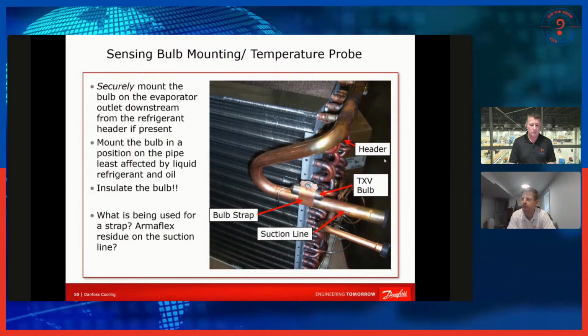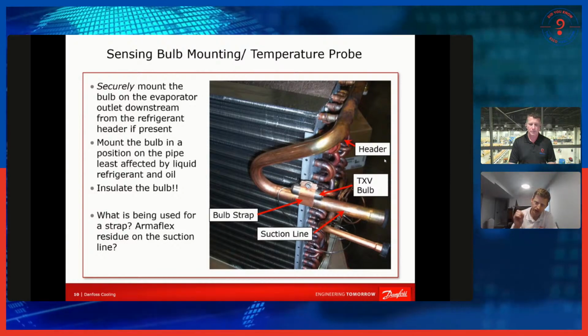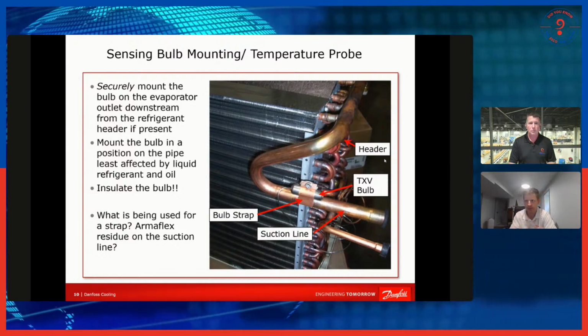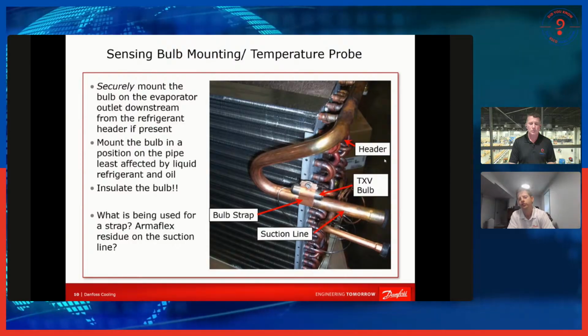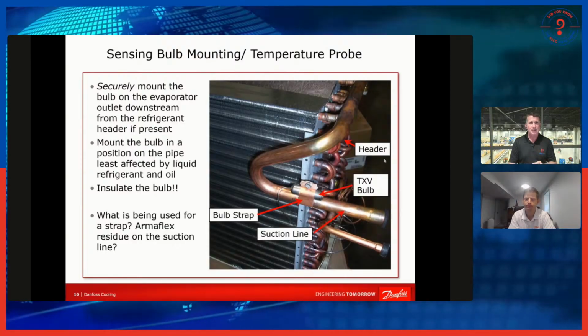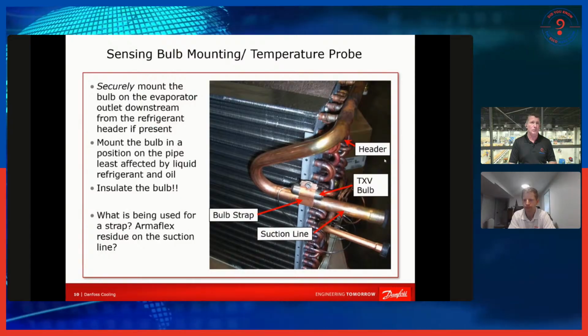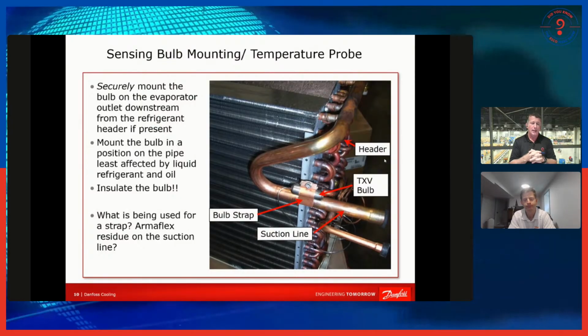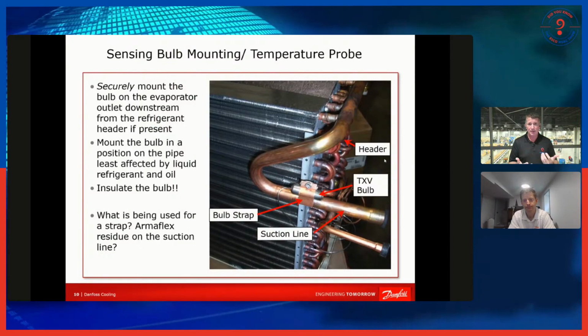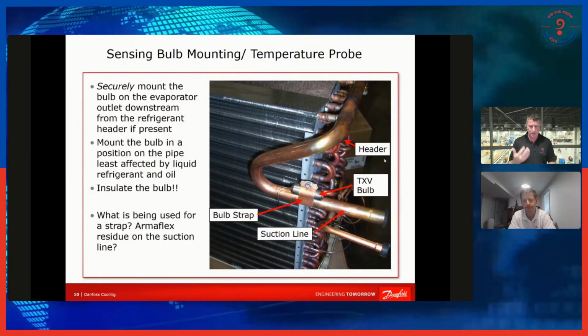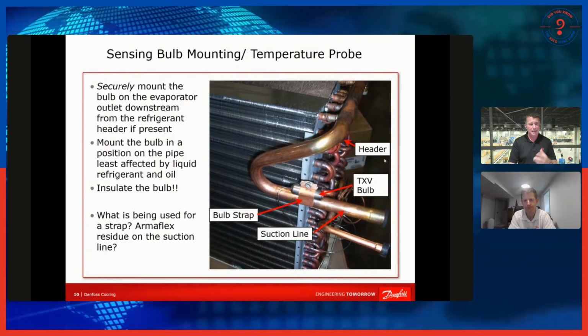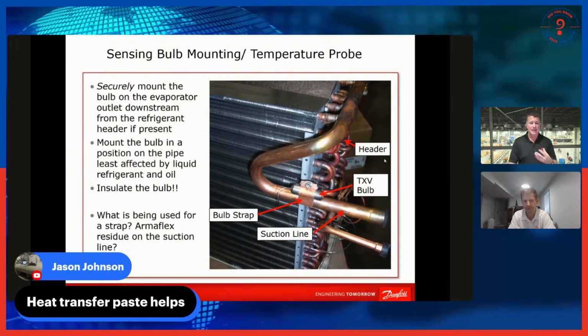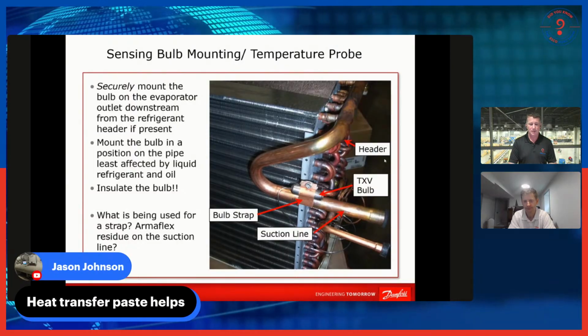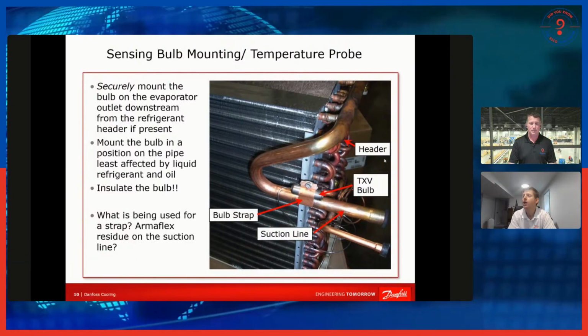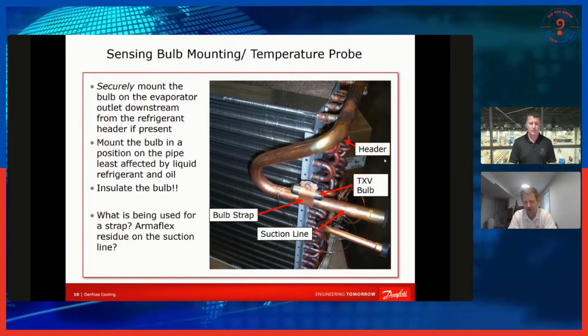But it's always better to do it because then you're getting a true measure of the suction line, and you're going to be more accurate in measuring superheat. Jason had another question that is a really good one, because I've encountered this before, and I'm not sure, and it might not even be something that can be answered. From a manufacturer perspective, is it acceptable to use a heat transfer paste in between a thermistor bulb and the tubing itself?